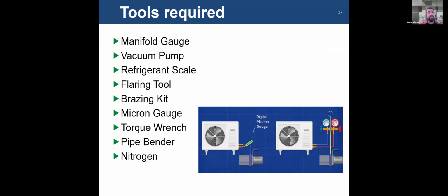Whether you are a contractor or a homeowner that thinks you want to put one of these in, there's a good amount of information you need. There's a good amount of tools that you need and require an initial investment. So you'll need a set of manifold gauges. You'll need a set of manifold gauges for each type of system or each type of refrigerant at the very least that you're working with. I even recommend a different set of manifold gauges for a standard residential split system and a mini split system.